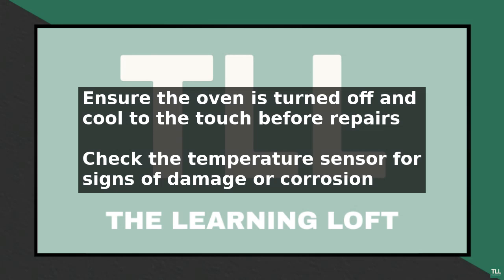Verify that all connections between the temperature sensor and the control board are secure and free of damage. If the connections are loose, tighten them according to the manufacturer's instructions. If the connections are damaged, they may need to be repaired or replaced. Next, check the oven's wiring diagram to ensure all connections are correct and not mixed up.